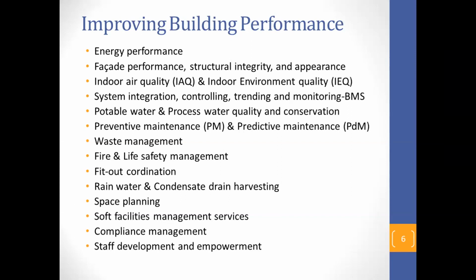Then preventive maintenance is a good starting point. But now we are into Industry 4.0, where predictive maintenance and IIoT are working very closely. Predictive maintenance, simple examples: for electrical systems, you can go for thermography. It's available in Sri Lanka. There are a few companies that can offer services. For motors, you can go for vibration analysis and signature analysis. And for generators, you can go for oil sampling, which gives you enough and more information about the condition of the generator, its parts, oil, and any contamination.